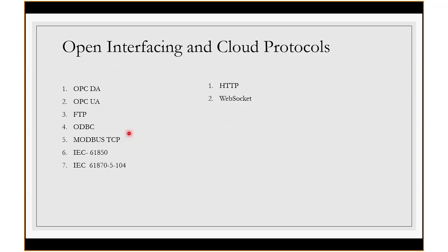The next one is IEC 61850. This is very commonly used in substation relays and smart relays. They use 61850, and these relays can be integrated into the SCADA to fetch the data. The same SCADA data can be shared with the load dispatch centers. Most smart electrical equipment can support 61850. Another important protocol, usually used for SLDC communications: most state load dispatch centers and central regulatory agencies fetch their data through the IEC 104 protocol. This is an important protocol nowadays - that's how all substation data is shared to the state load dispatch centers.